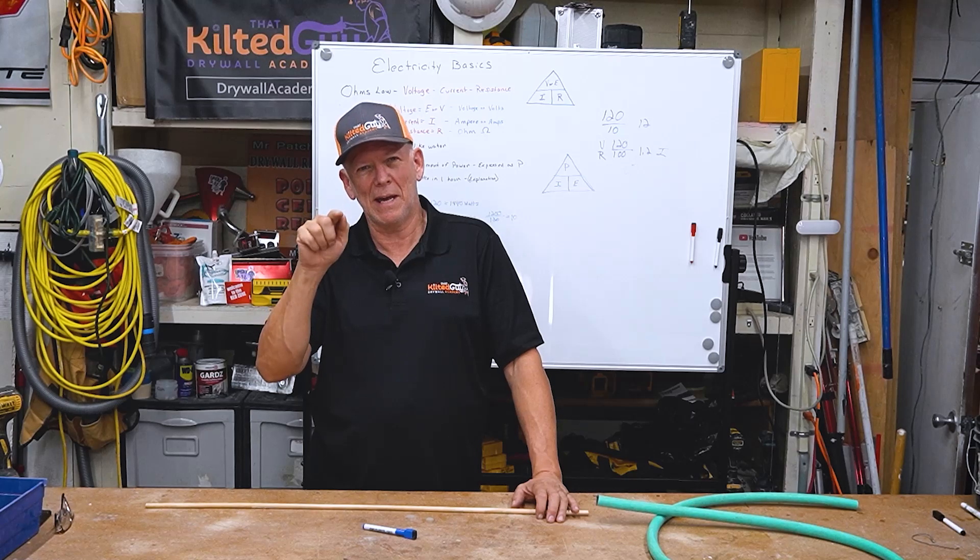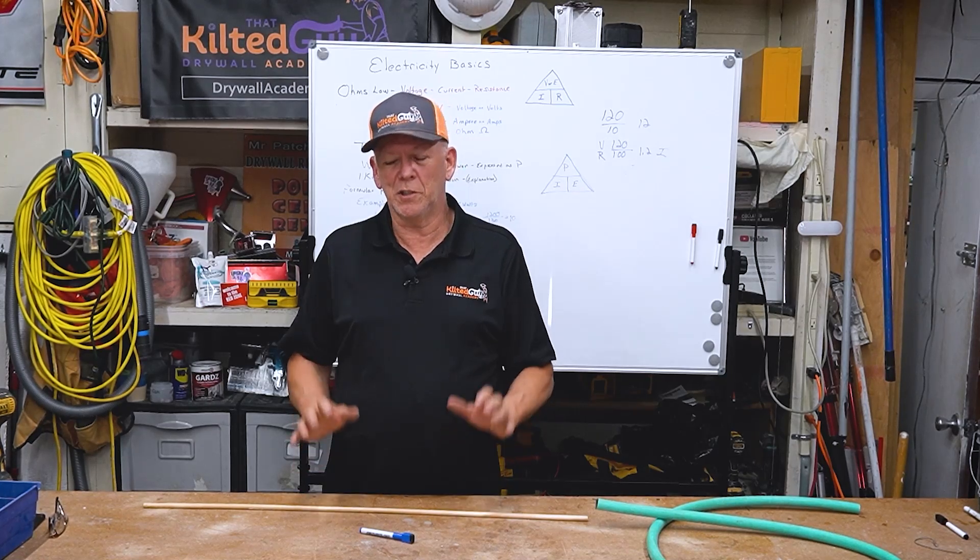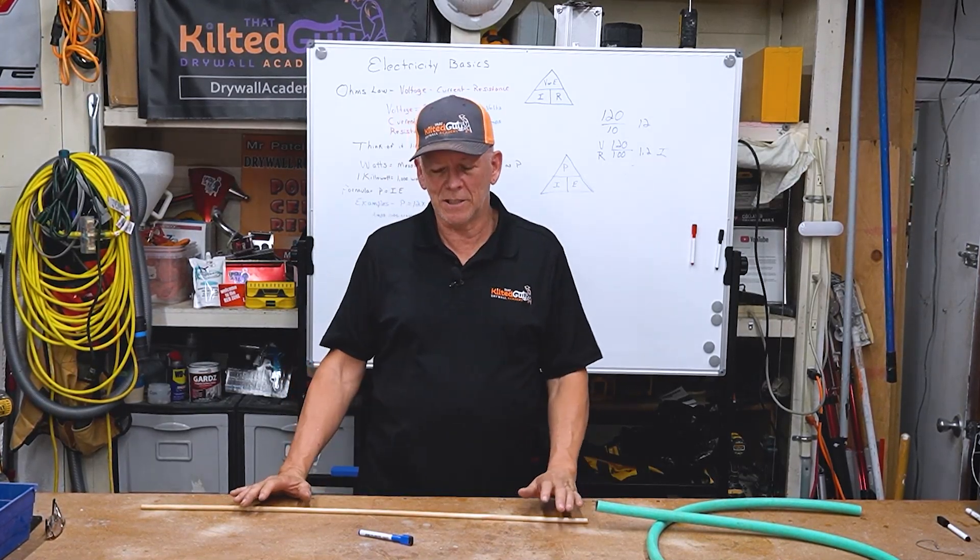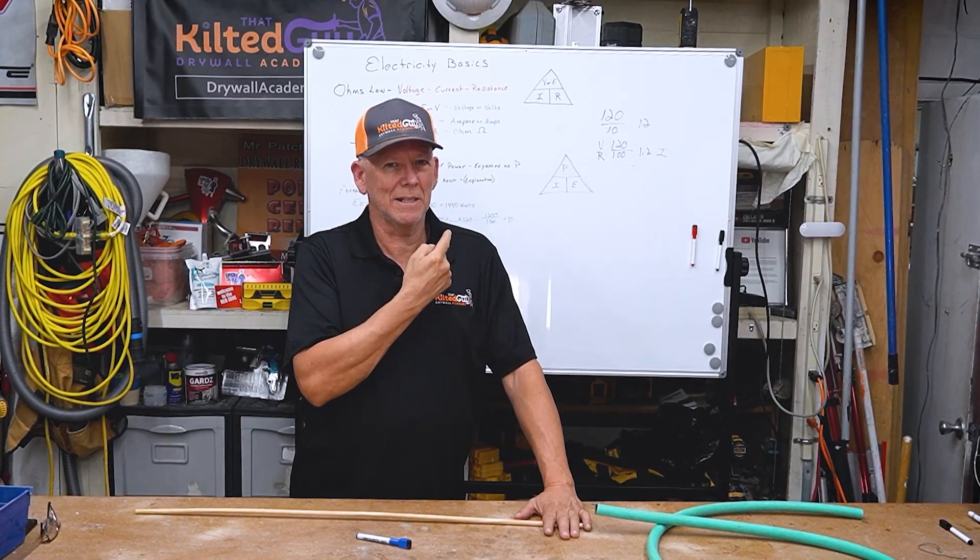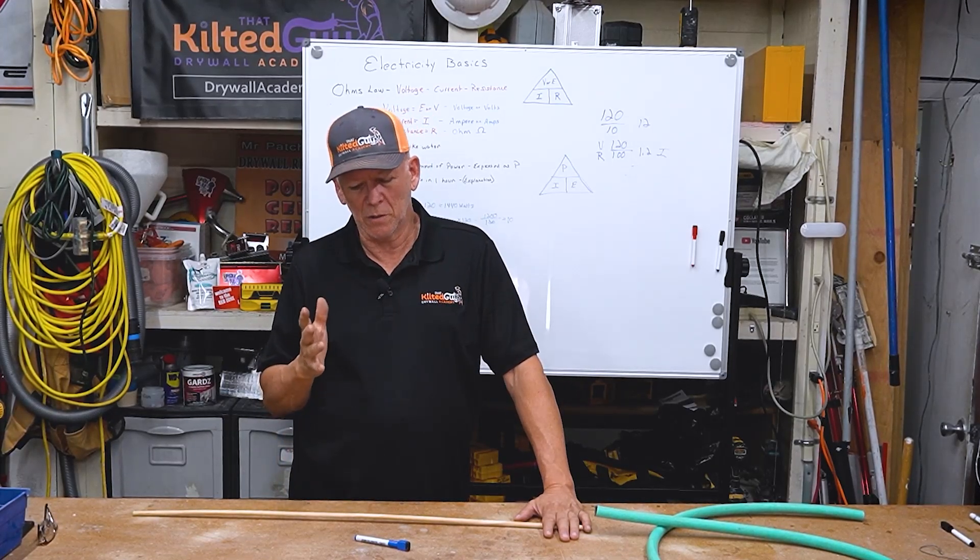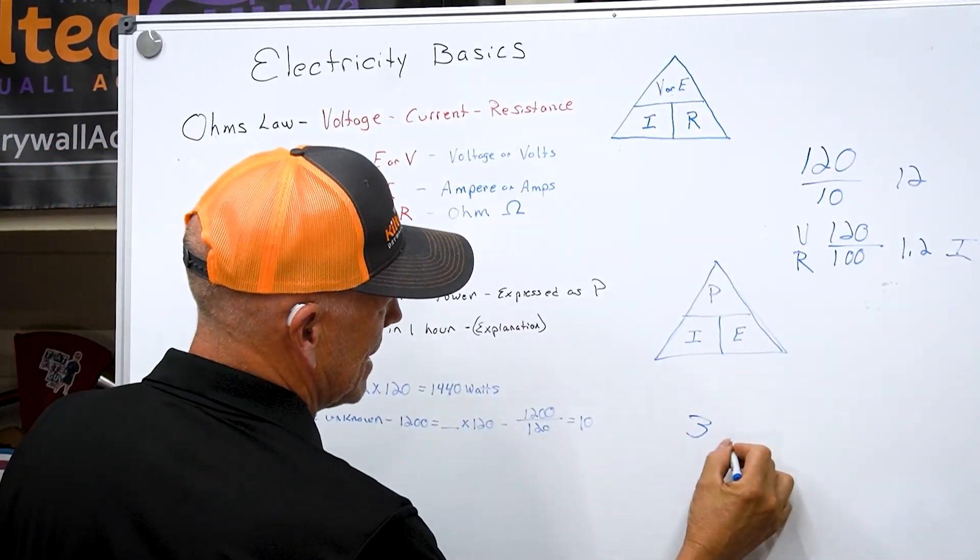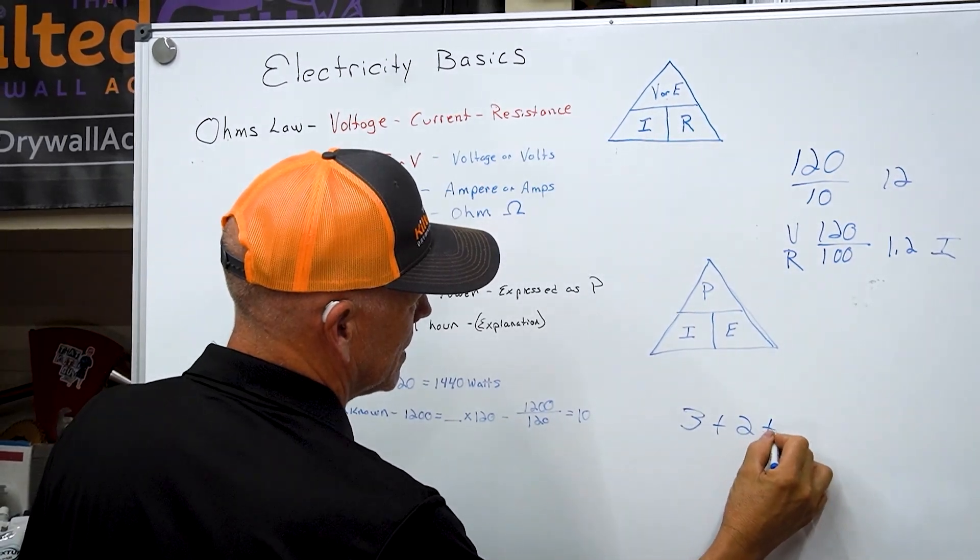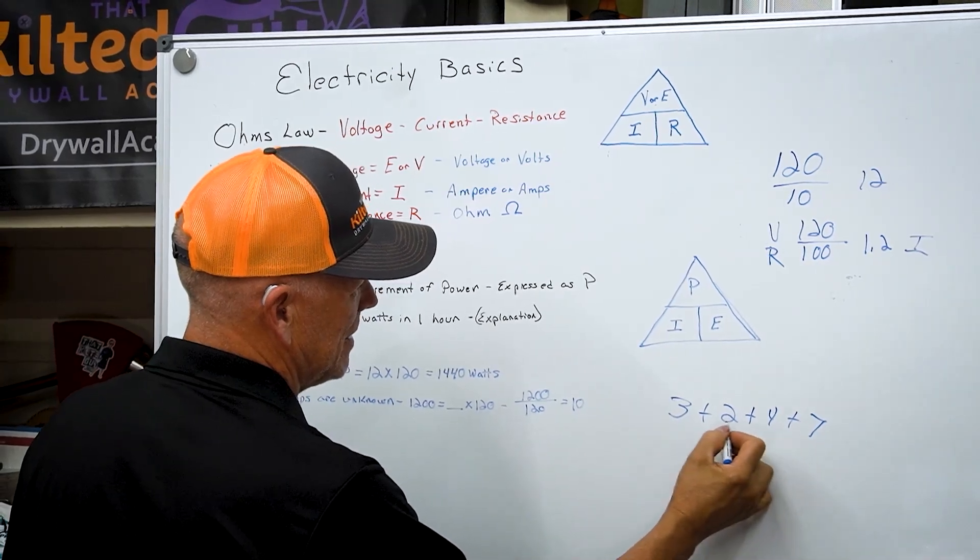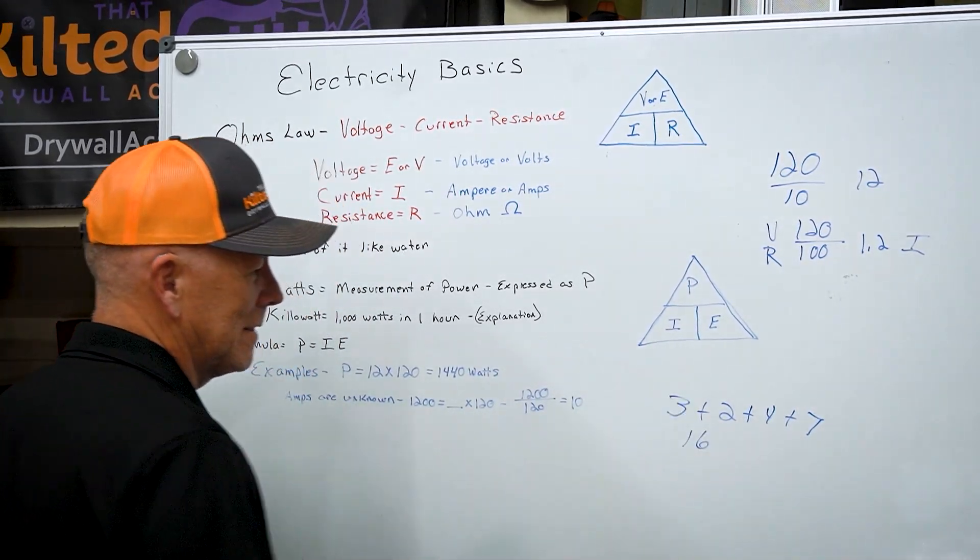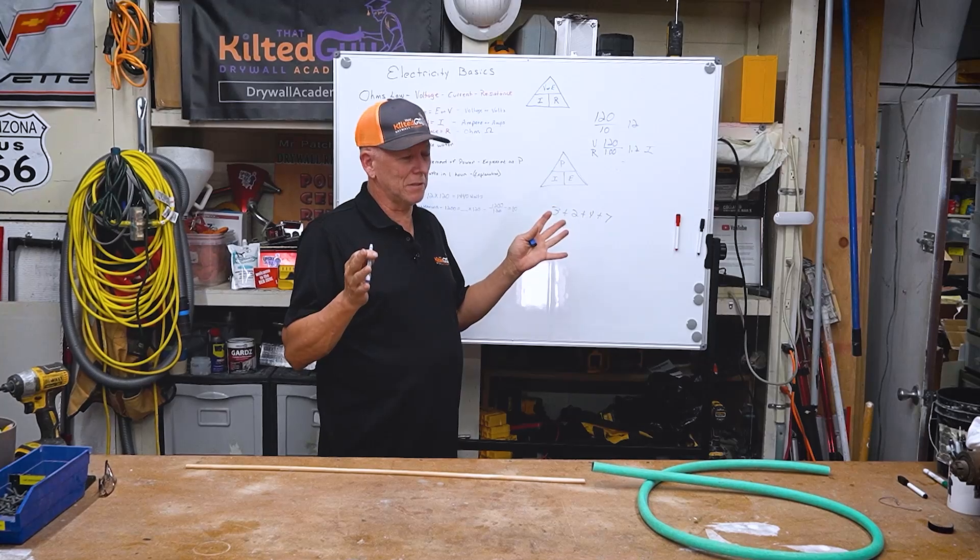Let me discuss another common kind of fallacy. A lot of times you'll hear that you shouldn't plug six things into one circuit, and that's to protect those of you who don't understand this right here. If you understand this and do the math right, you're pretty safe. So the reason is you don't want to overload it. So if you have a six-way and you plug in three amps plus two amps plus four amps plus seven amps, well right there you're at 5, 9, 16. You just overloaded that circuit. If you turn them all on at once, you'll either trip the breaker or you could melt things.